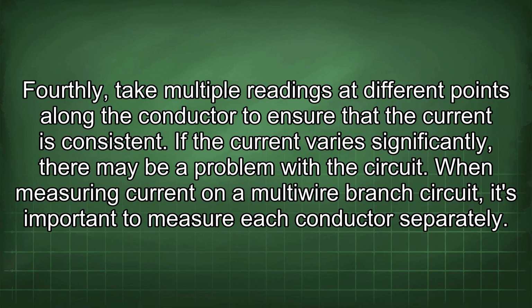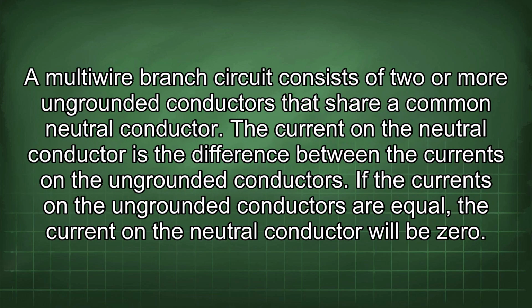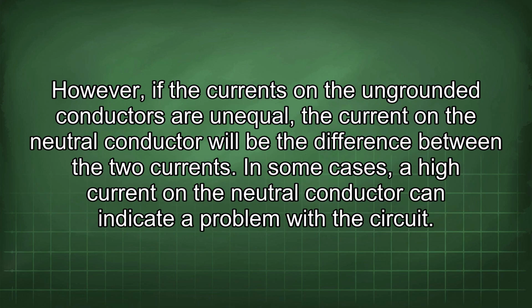When measuring current on a multi-wire branch circuit, it's important to measure each conductor separately. A multi-wire branch circuit consists of two or more ungrounded conductors that share a common neutral conductor. The current on the neutral conductor is the difference between the currents on the ungrounded conductors. If the currents on the ungrounded conductors are equal, the current on the neutral conductor will be zero.